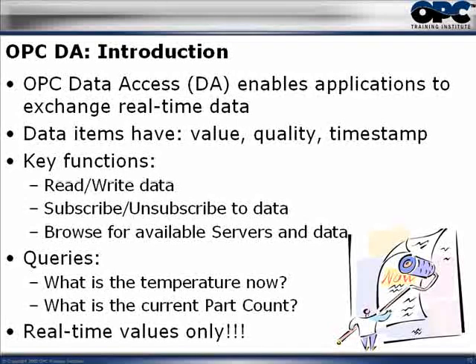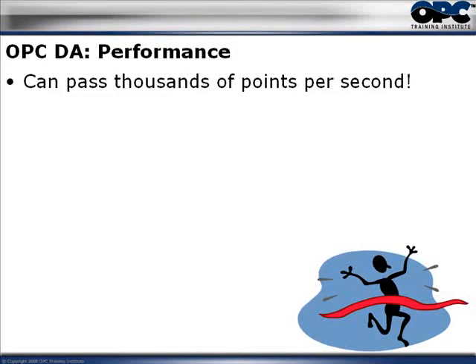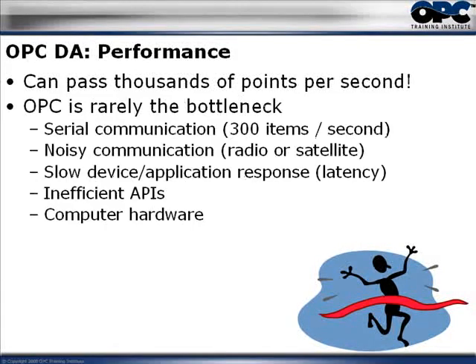So how fast is OPC anyway? OPC servers can pass thousands of points per second — in fact, some pass hundreds of thousands of points per second. But that doesn't necessarily mean much, because the bottleneck typically occurs elsewhere. For example, with serial communication you're typically going to see around 300 points per second. Once data gets into the OPC server you can send out hundreds of thousands of points per second, but the serial communication on the input side will slow things down.